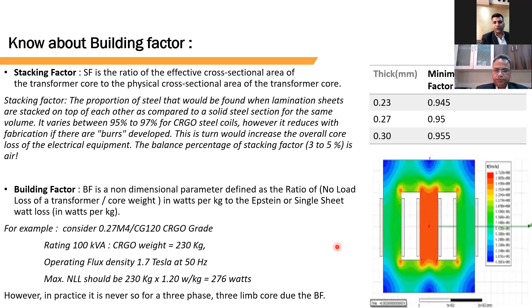With this picture on the right side, I want to show that wherever there are these dark blue lines, flux is going to be dissipated because of the joints and air gaps. So these are the areas where our building factor is going to play a role. Of course, there are other areas shown on the right side in red color also. These are the areas where we need to consider this loss in power loss, which is going to affect our no load loss calculation. So in the next slide, we will understand in detail the building factor calculation. Sir, can we move to the next slide?